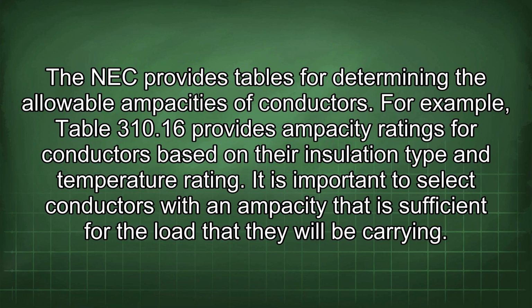The NEC provides tables for determining the allowable ampacities of conductors. For example, Table 310.16 provides ampacity ratings for conductors based on their insulation type and temperature rating. It is important to select conductors with an ampacity that is sufficient for the load that they will be carrying.